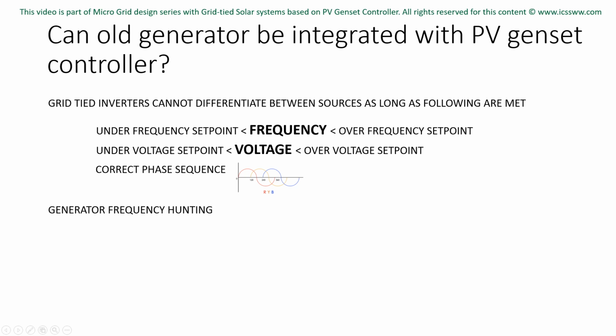Grid-tied inverters cannot differentiate between old or new generators as long as the following electrical parameters are within the acceptable range of the inverter. Frequency must be between the over frequency and under frequency set points defined in the inverter. Voltage must be between the over voltage and under voltage set points defined in the inverter. The phase sequence should be appropriate. Usually, a well-maintained old generator will provide the appropriate electrical parameters mentioned above.